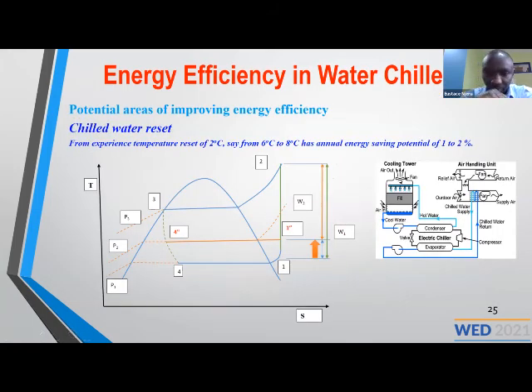So we have chilled water reset. As we have seen, in these air handling units, for example, if the demand for the water temperatures is not very high, you can reset the temperatures up. In the TS diagram, you've seen this line is proportional to the amount of work done by the compressor, or the energy consumed by the compressor. In such a case, you can reduce the work done by the compressor by resetting the temperatures slightly higher than the requirement, probably by 2 degrees or 8 degrees. And in such a case, you can have potential savings of 1 to 2% of the annual energy savings if you are operating at very low temperatures. So this is one of the areas where you can save energy.